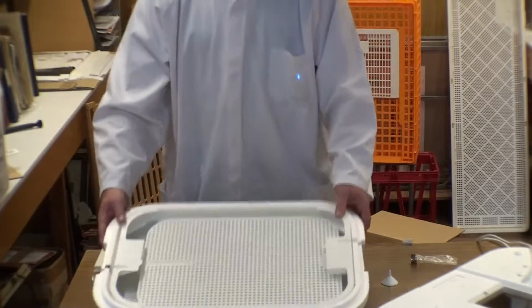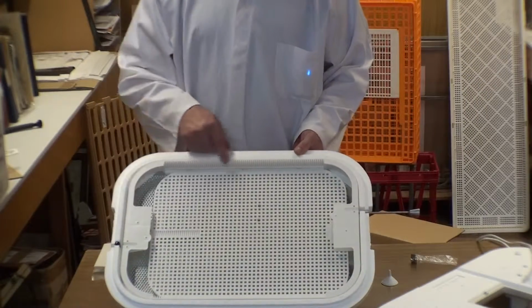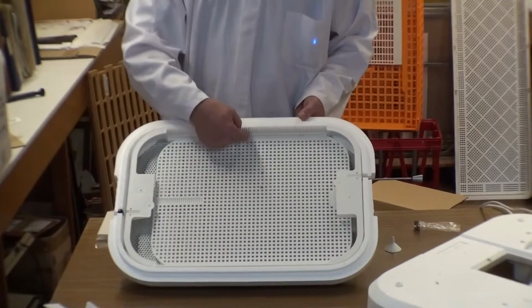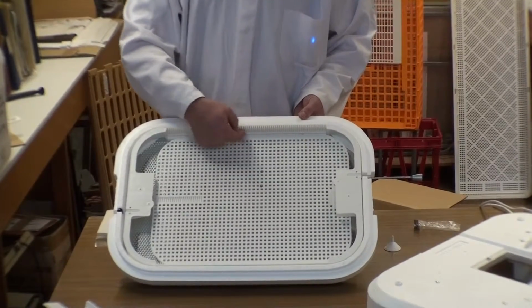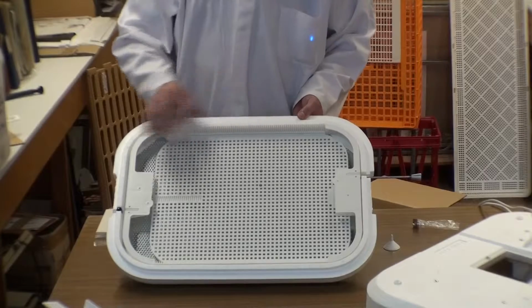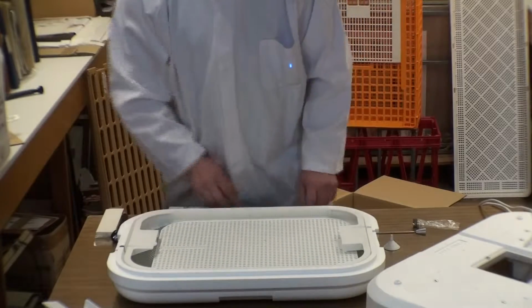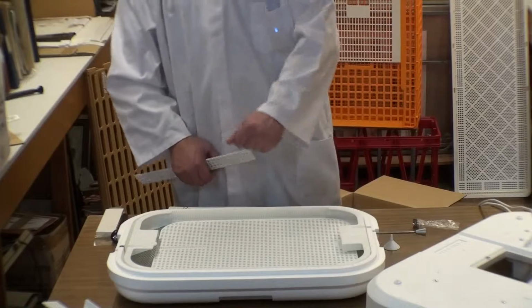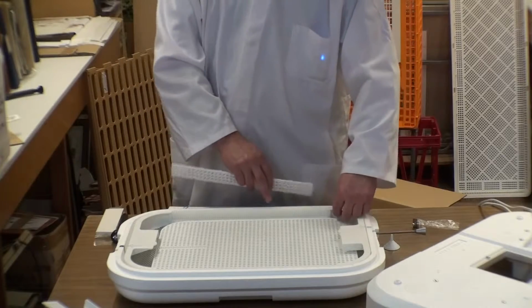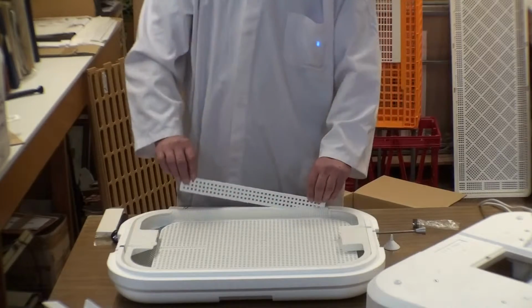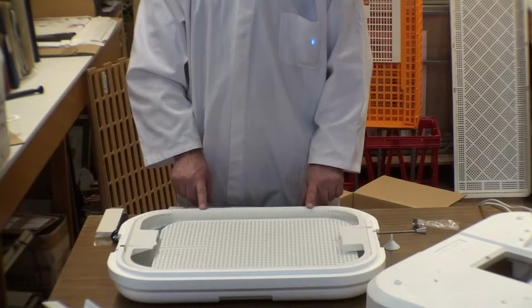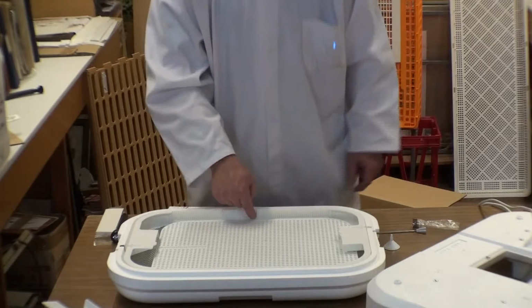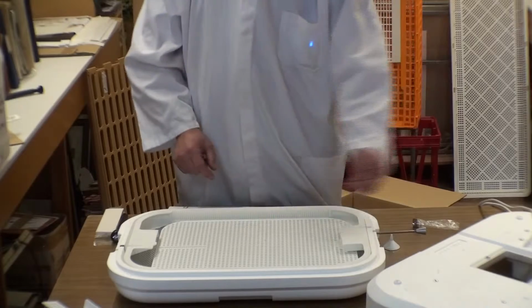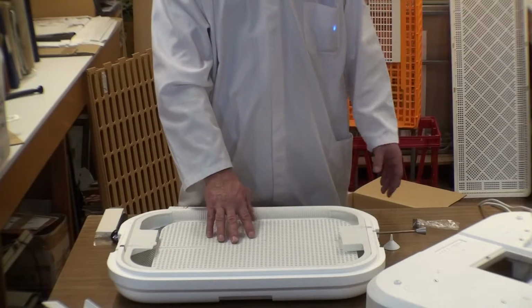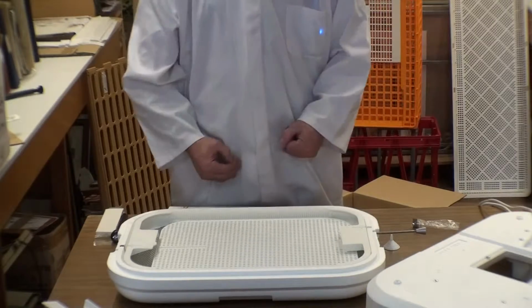Now, it's an important thing that when you put the turner in, either the semi-automatic or fully automatic, there should be a little gap along the side of the tray here, about 2 millimeters wide. Okay, we make it deliberately so that it's never too tight, but sometimes you'll find the mouldings will leave it being a little bit too loose. So all we do is we have an extra divider in there that we pop down the side, so there's about a 2 millimeter gap. This allows for nice smooth operation of the tray, and at the same time has the tray supported on the rollers.